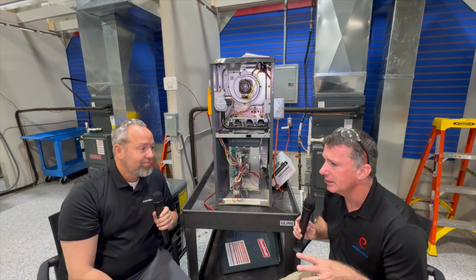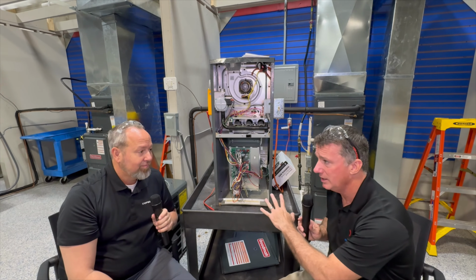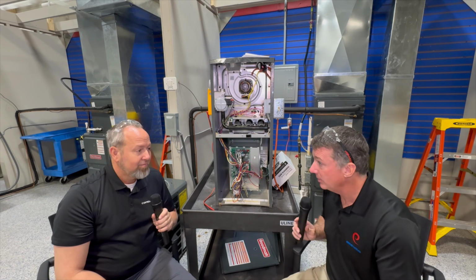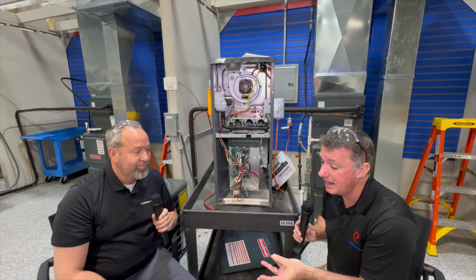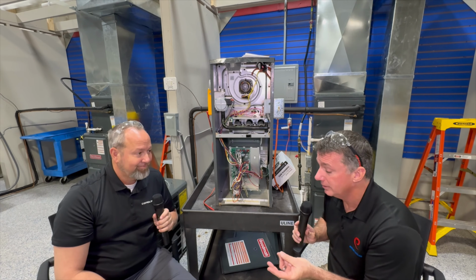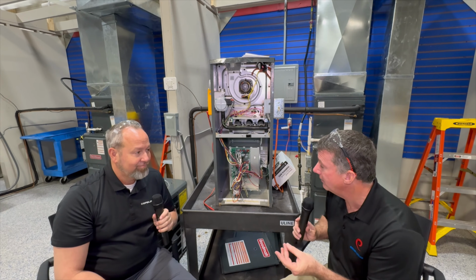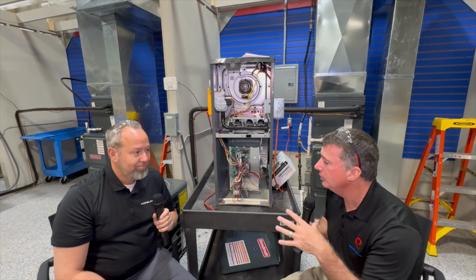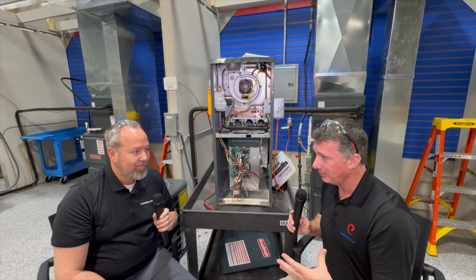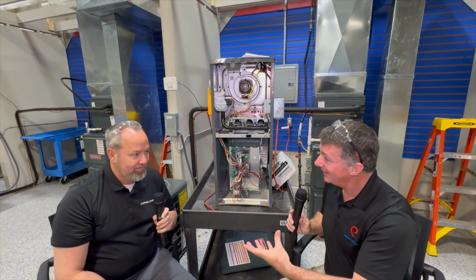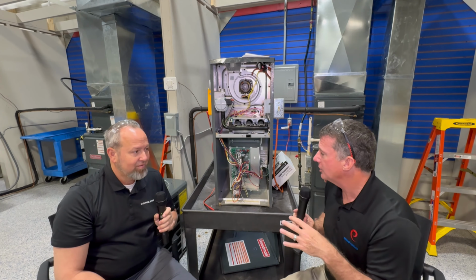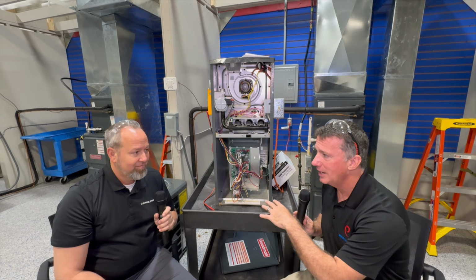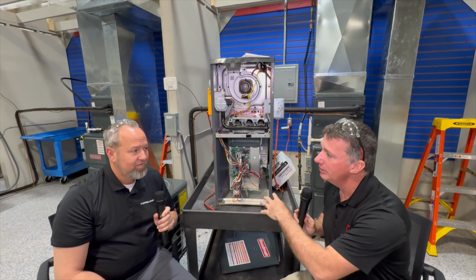It's very interesting—the actual wire connections on those Molex plugs really depend on the manufacturer. You could have your limits, your flame rectification, a variety of things in different combinations. So you've designed the board so you don't have to have the adapters, because previously we used adapters depending on different manufacturers. Now you're actually looking at those signals coming in, so you've traced all the different combinations.